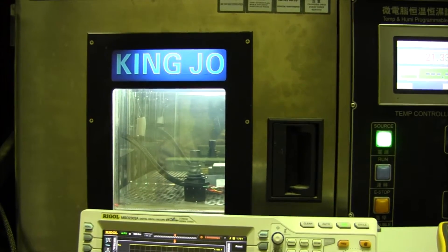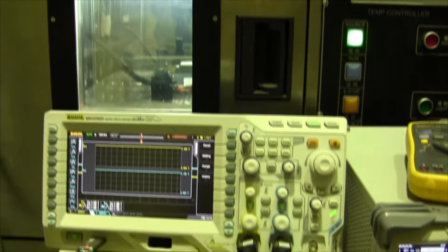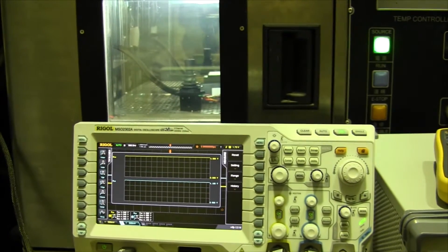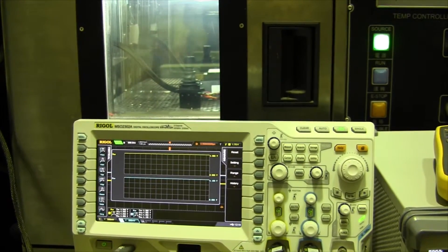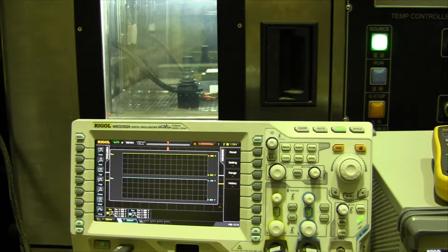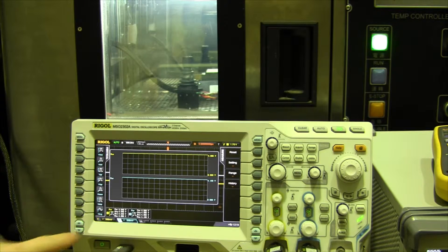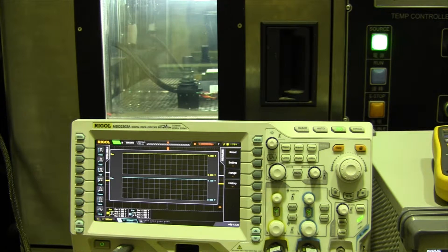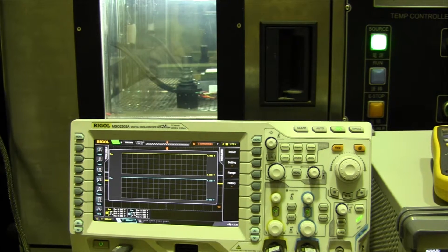Okay, and what we are doing is monitoring the voltage on a scope and we've got a bit of a history running there. So we'll be able to see about every 5 minutes I'm going to check whether we're going to have any issues. We have an average running there as well for a minimum and maximum as well. So that's going to log our min and max across the temperature cycling test.